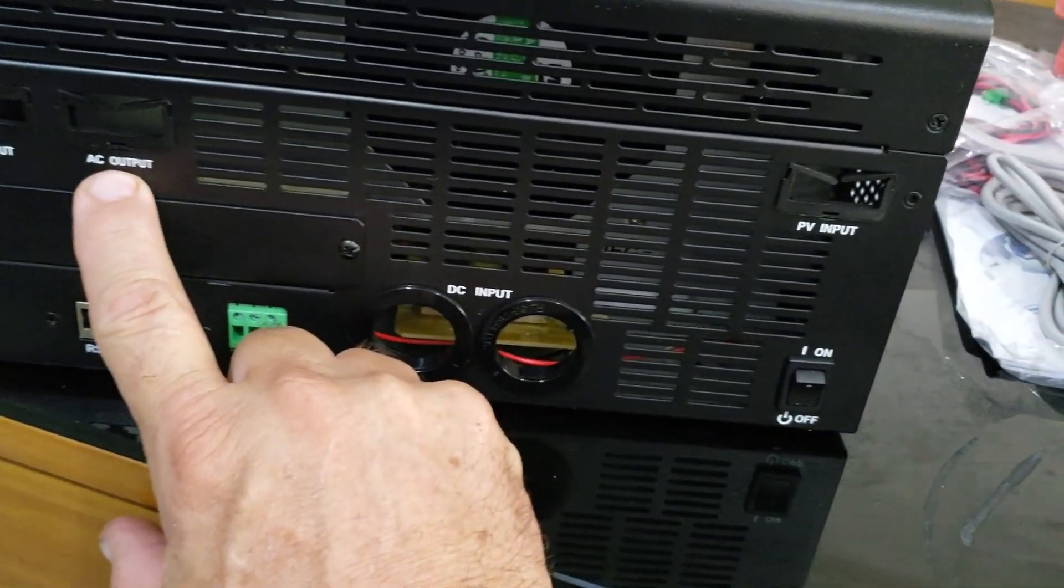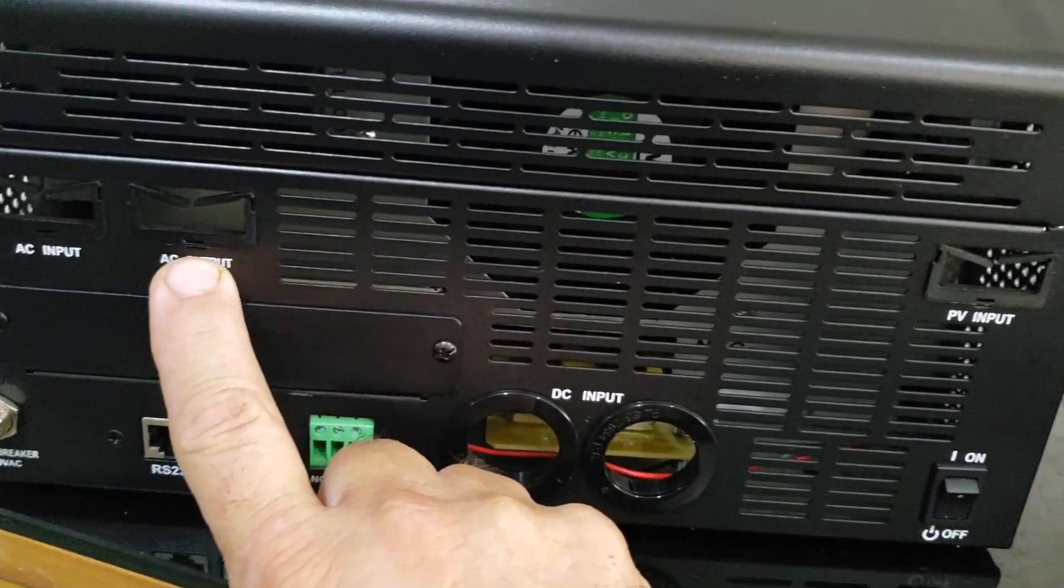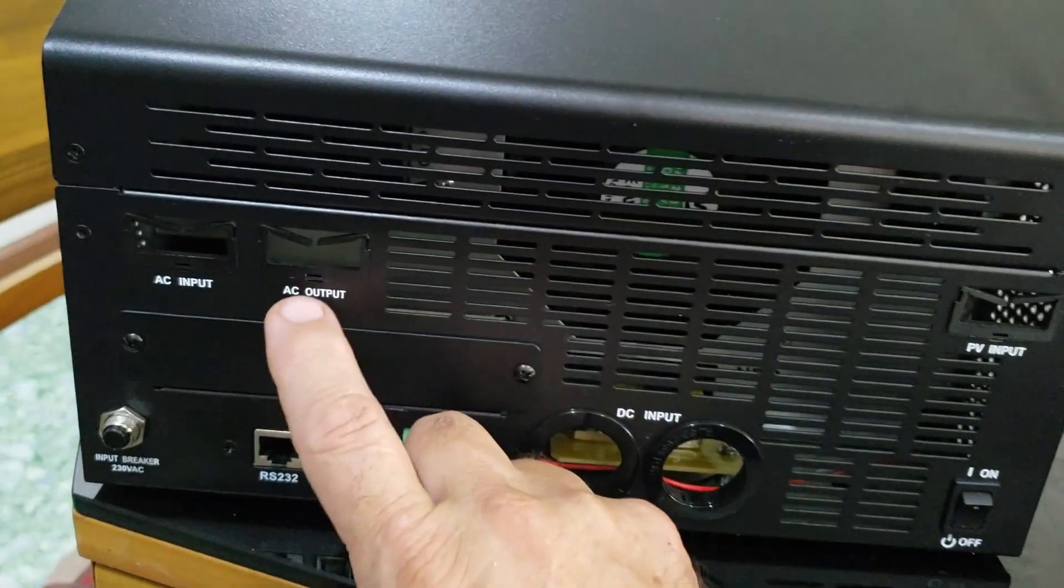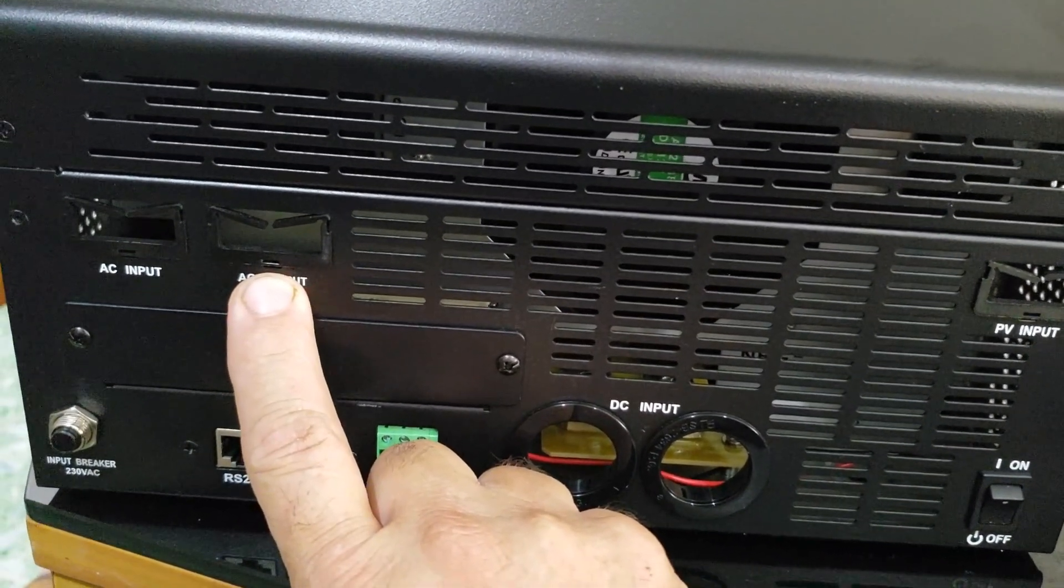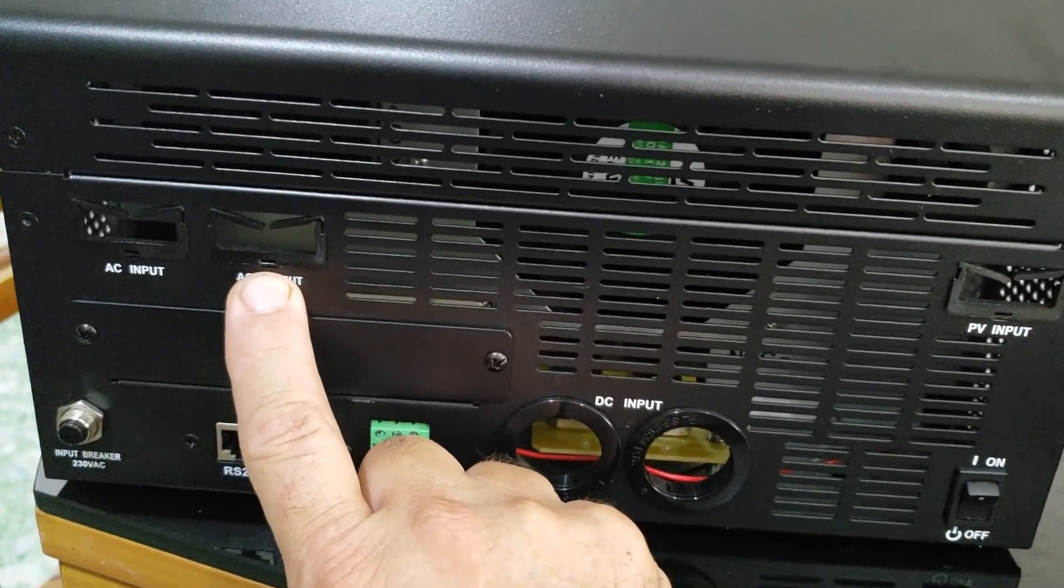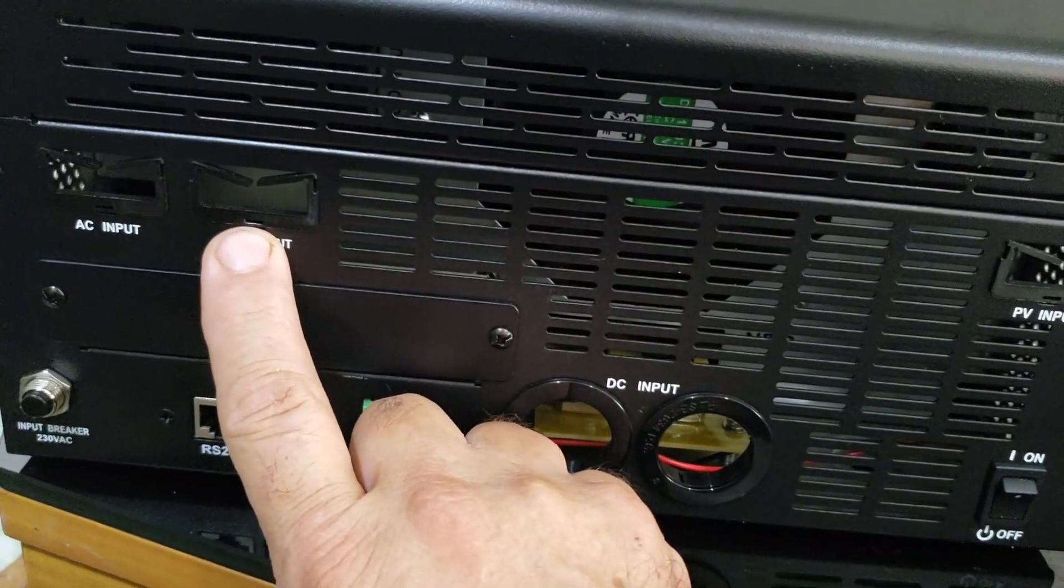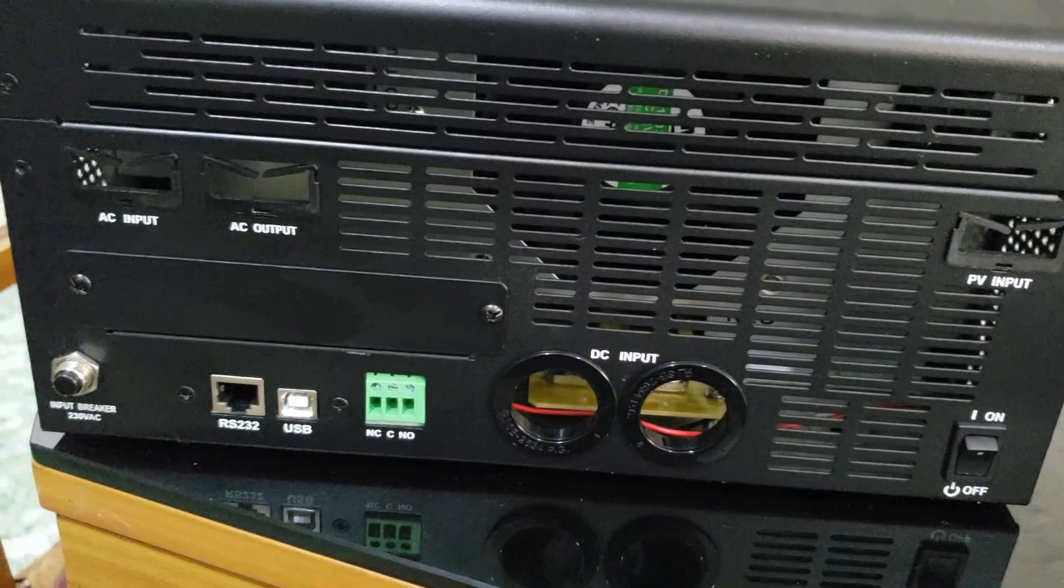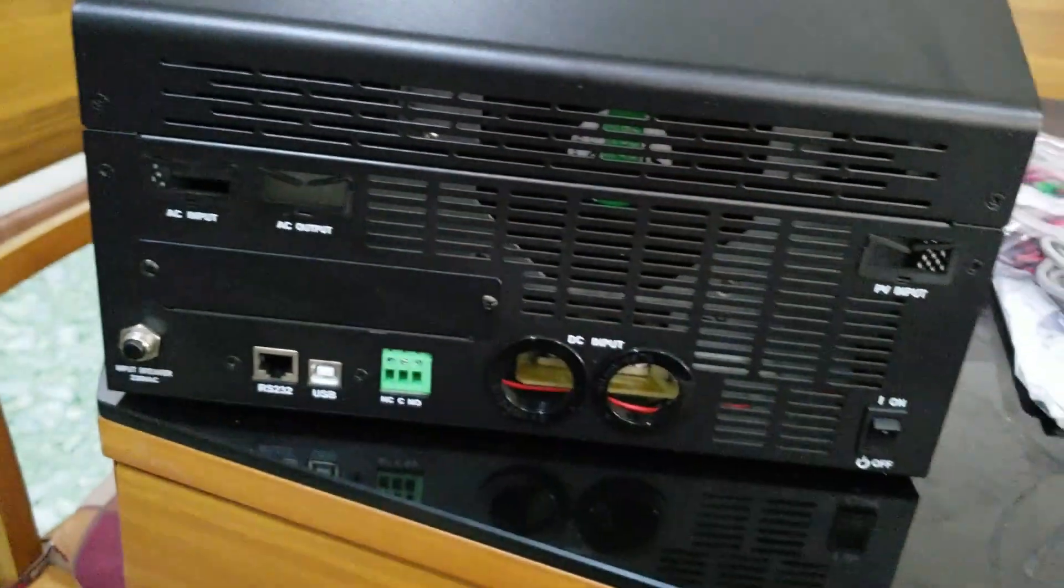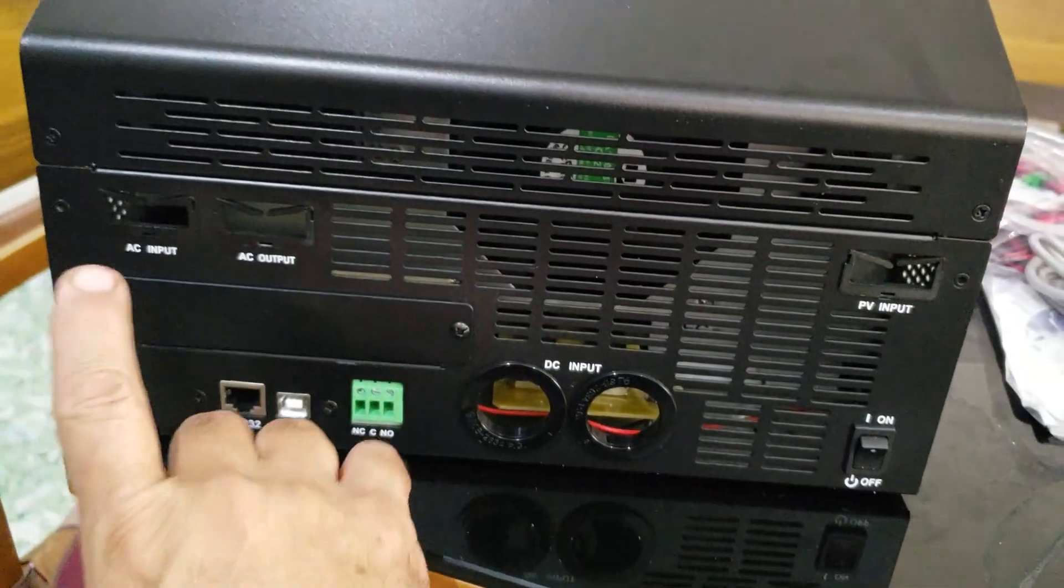Now over here you have AC output. That output is what will go to power all the things that you want to power off of this unit. Maybe you want to take it to a service panel and split it out off breakers of the different directions it's going. Maybe you want to put a main in which is what I'm doing. I've already bought a service panel that's going to be just for this and it's going to have a main. And then from that main it'll have breakers for the different directions that I want to send this power. You can put a main in only and then send that main on to an existing service panel maybe you have. So that'll be where that goes.